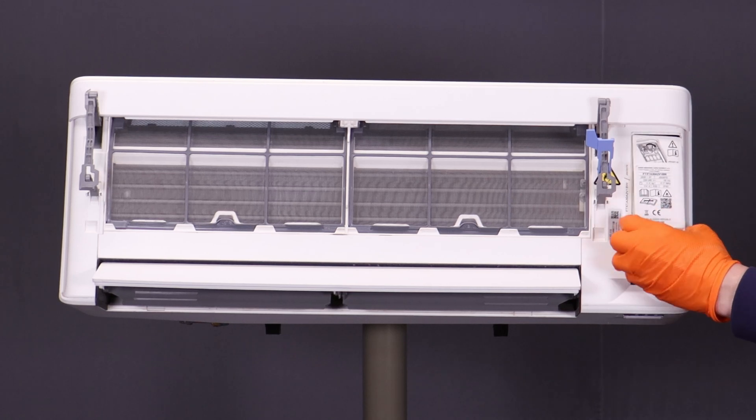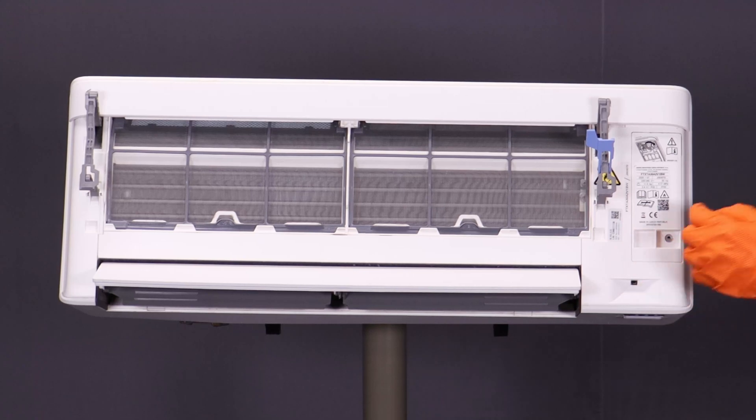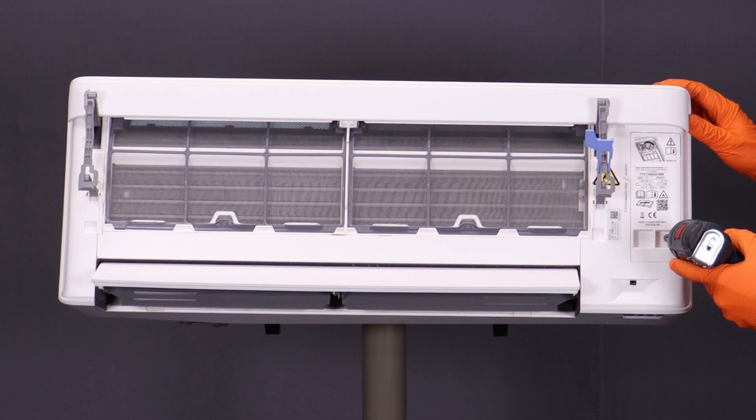Electrical cover is slid back on. Remember the wires? If outer shell wires are left disconnected, unit will function, but the front panel will fail to move during power off or on cycles.